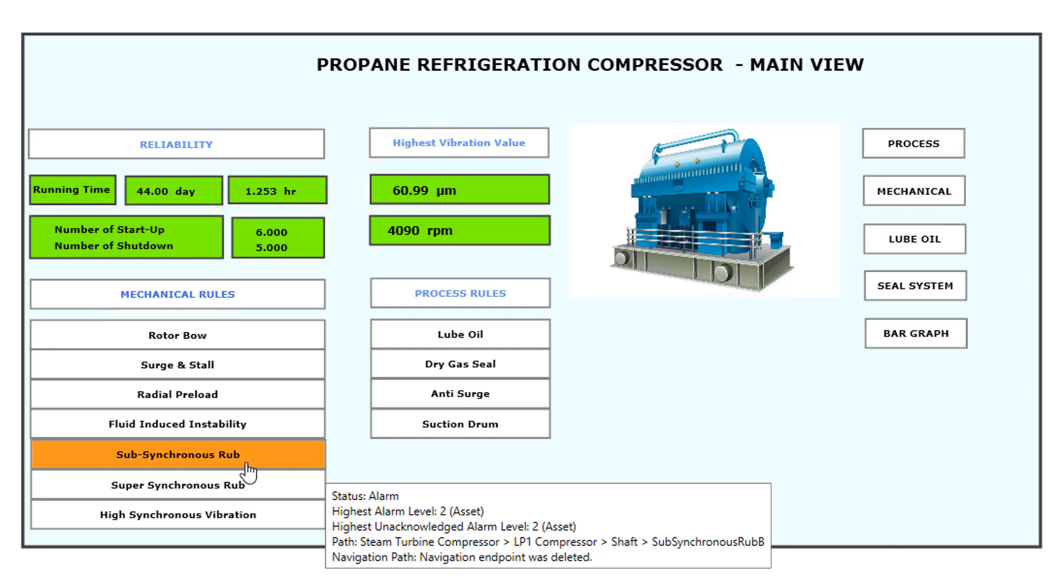The engineer then confirms the sub-synchronous rub originated from the Bentley Nevada decision support analytic listed under the mechanical rules and takes the next step to investigate.